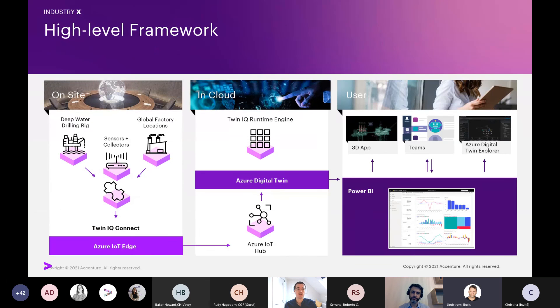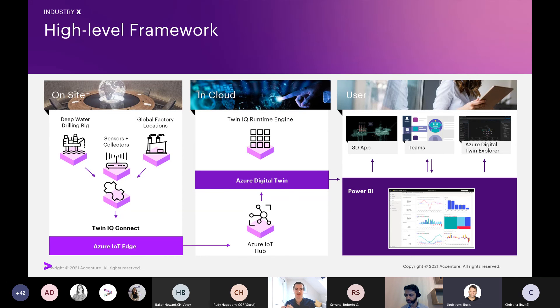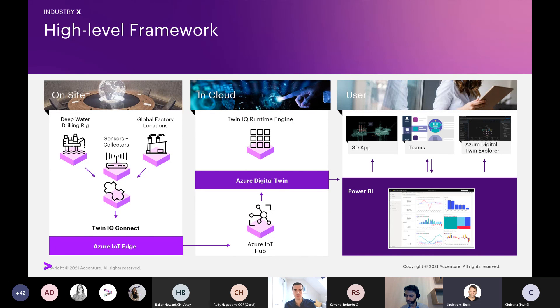The solution is built up of three main areas. First, the on-site element contains data acquisition through sensors or existing systems and connectivity to the Azure IoT Edge. The second is the cloud portion, which takes that near real-time data feed of the equipment and feeds it into the Azure Digital Twin. Finally, the user interface includes not only 3D visualization of contextual data, but also Teams integration to share and communicate decisions and insights, Power BI to generate deep insights, and Digital Twin Explorer for interrogation of that data. The real power comes into effect when the twin not only streams and identifies anomalies, but also runs simulations and identifies new opportunities for optimizations that were previously unknown or undiscoverable.